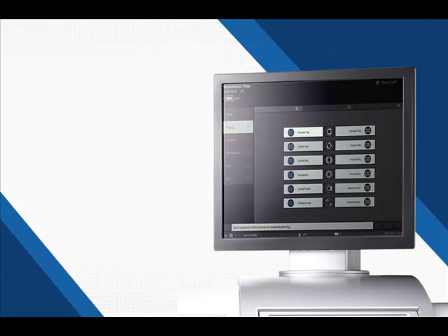Now to go a little more into detail. The cataract soft fit interface is on the right. The LASIK interface is on the left. For the right one, using the soft fit, there is a unique collar that the contact lens locks into, and the silicone skirt is longer. For LASIK, you do not require the soft fit insert. The collar that it locks into is not there, so if you put a soft fit into the LASIK one, it'll simply fall right back out. And the silicone skirt is shorter in length.